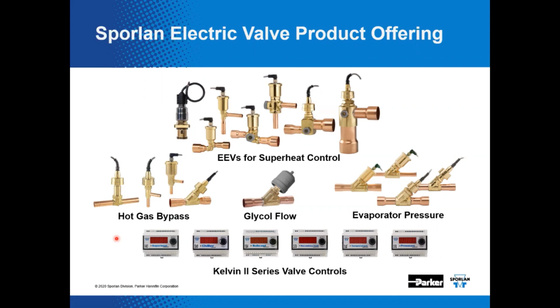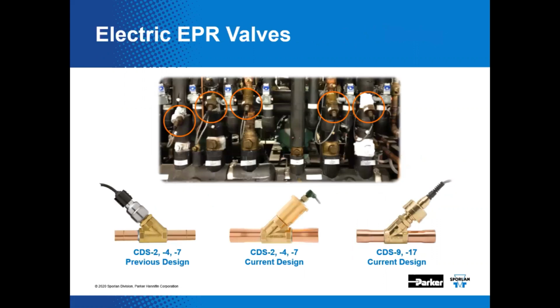You can typically take one of the electric EPR valves, one of the pressure regulating valves. They'll control well down to maybe as low as 10% or so. Oh wow! Of their maximum rated flow. And for the expansion valves, they can readily control down to about 20% of their maximum rated flow. And then as another thing, again, we mentioned this earlier, these can be monitored and controlled remotely if the right accessories are in place on the job. Indeed. And that's something that a mechanical EPR is going to be hard pressed to be able to do. Yep. Not so capable with a mechanical device.